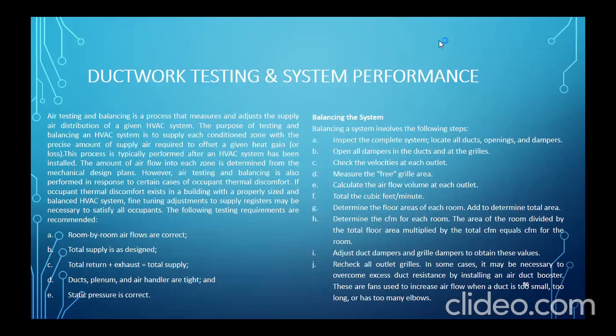So, next is, hindi lang design, hindi lang installation, fabrication, conducting, hindi lang pagbebenta, pati yung testing and system performance. Air testing and balancing is a process that measures and adjusts the supply air distribution of a given HVAC system. The purpose of testing and balancing of an HVAC system is to supply its conditioned zone with the precise amount of supply air required to offset a given heat gain or loss. This process is typically performed after an HVAC system has been installed. The amount of airflow into each zone is determined from the mechanical design plan.